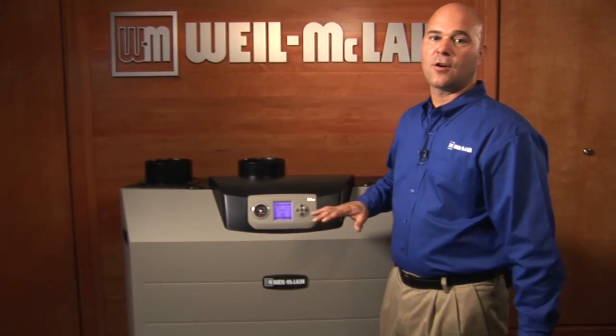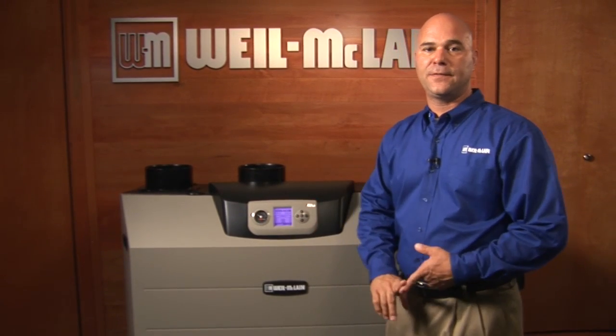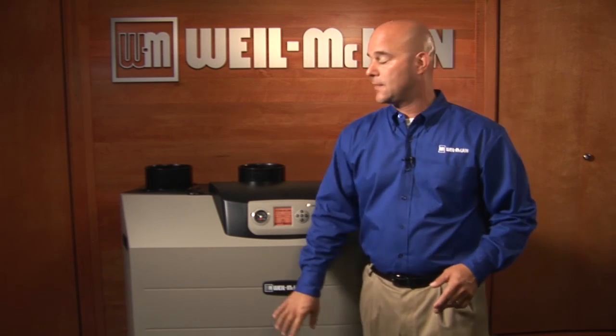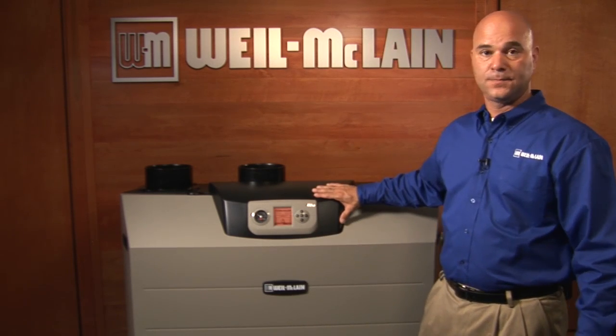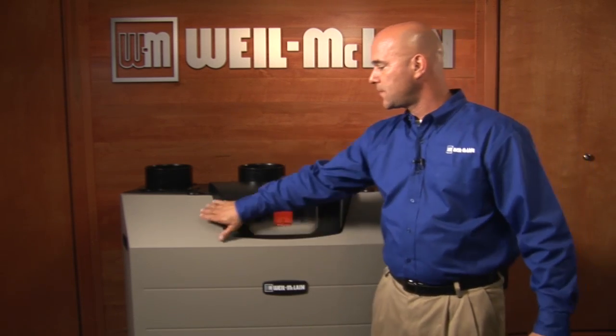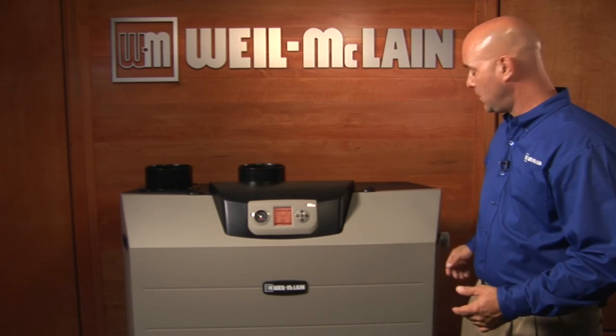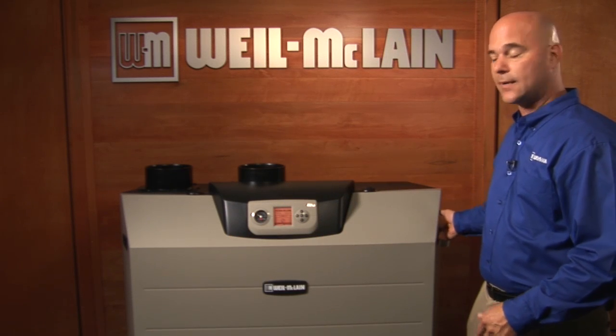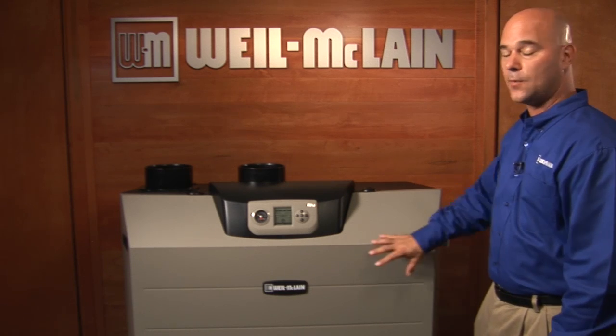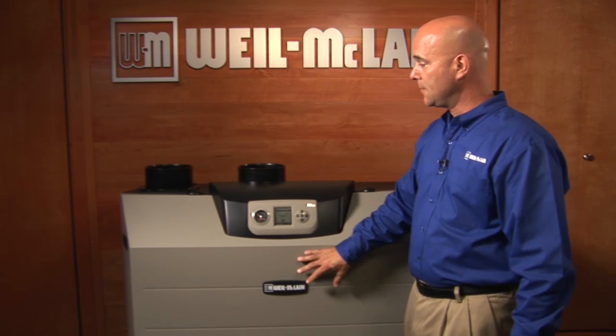In this segment, we're going to talk about the ultra commercial. There's a 550,000 BTU boiler and a 750,000 BTU ultra commercial. The boiler itself, this front jacket portion is removable. There's handles in the side of the jacket so you can pick it off and take it out of your way so you have access to the heat exchanger compartment.